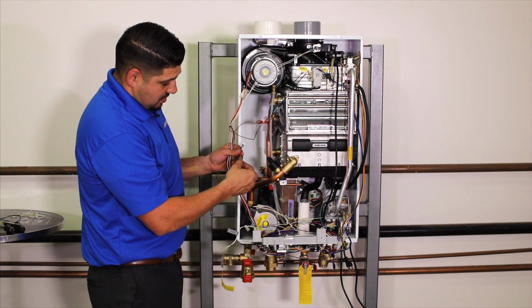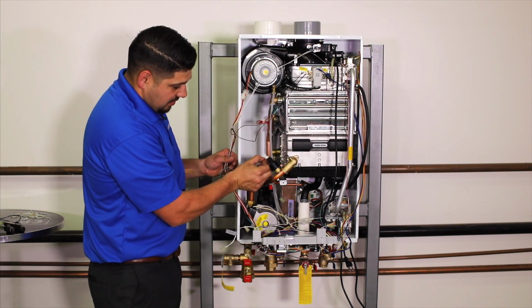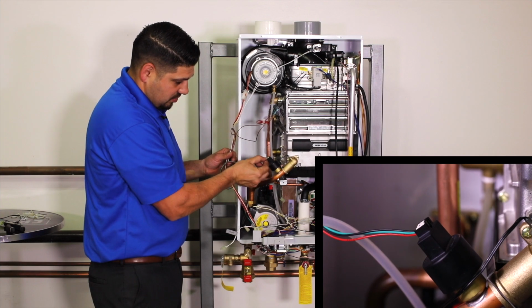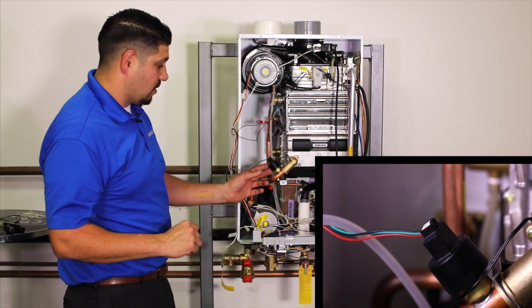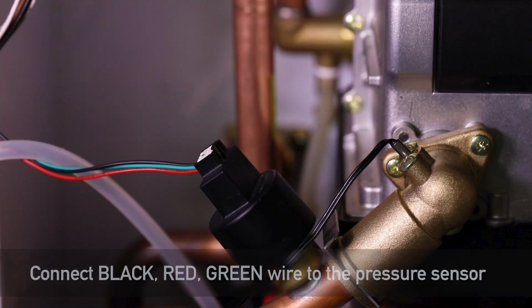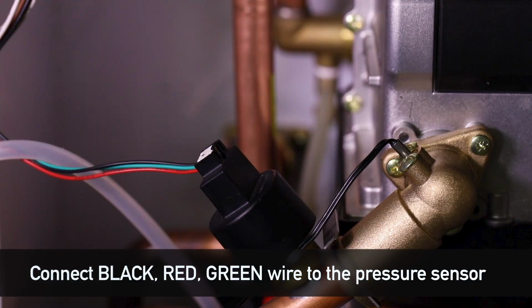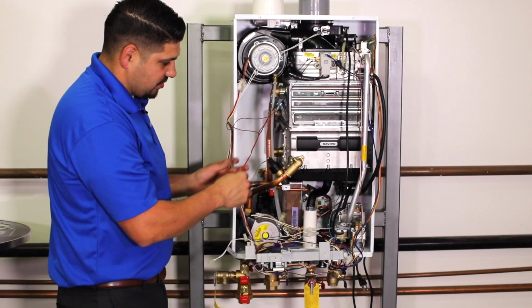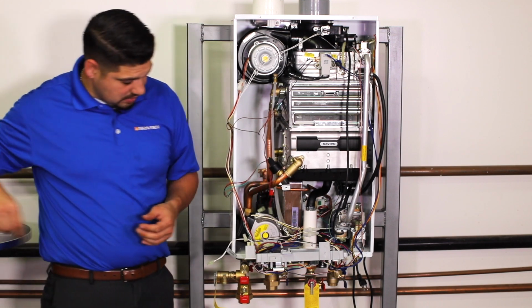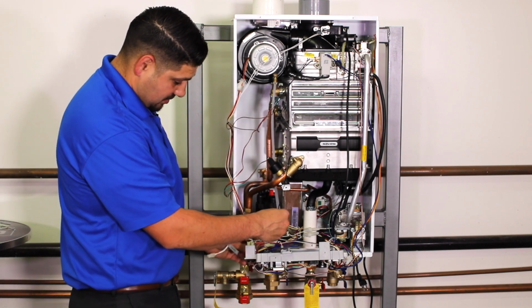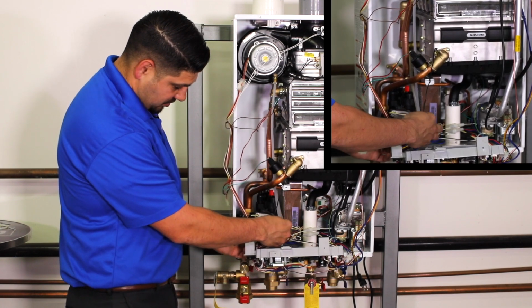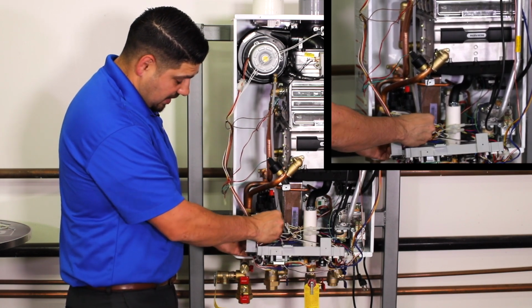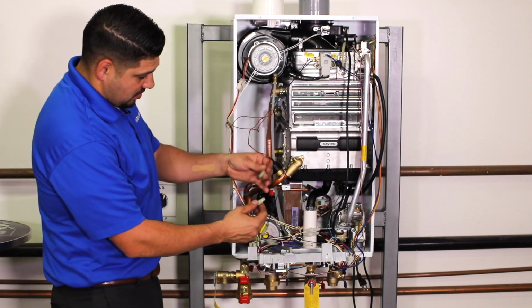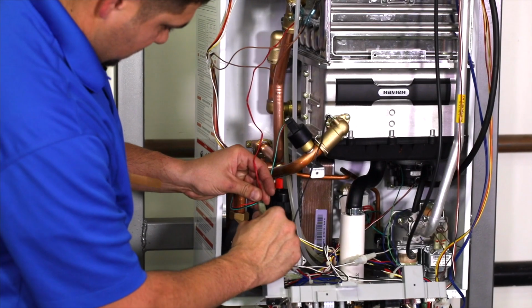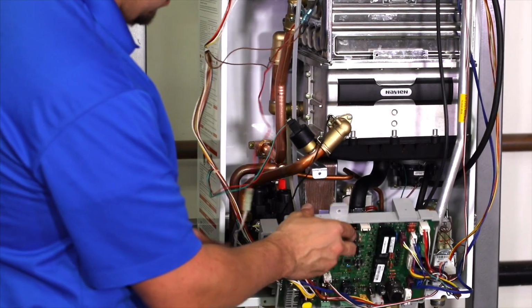We have a red, green, and black wire. That's going to connect to, make sure it's properly plugged in, that's going to connect to your pressure sensor. Two temperature sensors. Now, one is black, one is red. So we're going to go ahead, and you can kind of tell which one's which because it's a little bit longer and shorter. The connections are the same, so you can crisscross them. We're going to make sure everyone goes here to your supply. So we got them all connected properly.